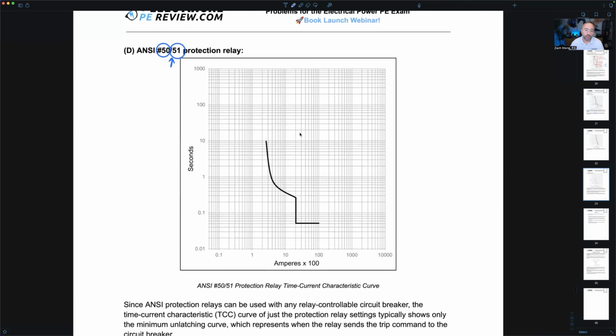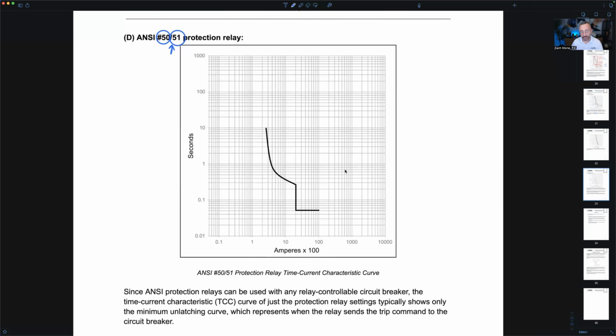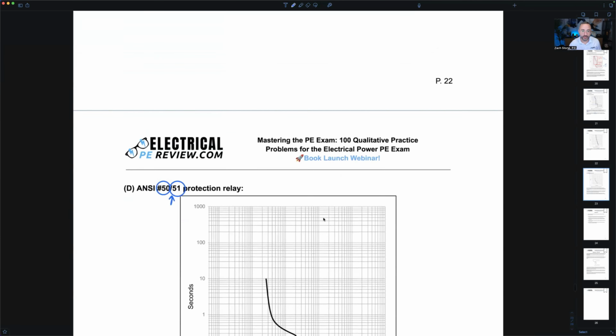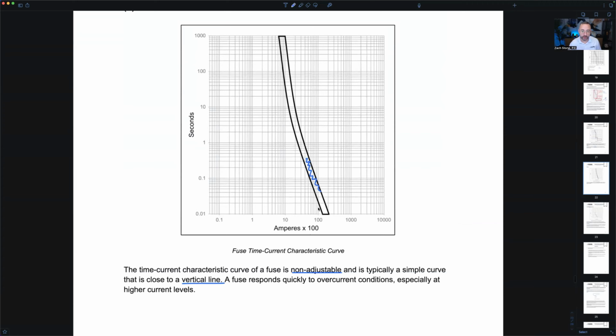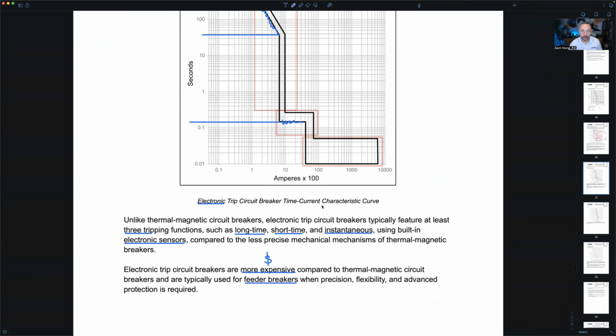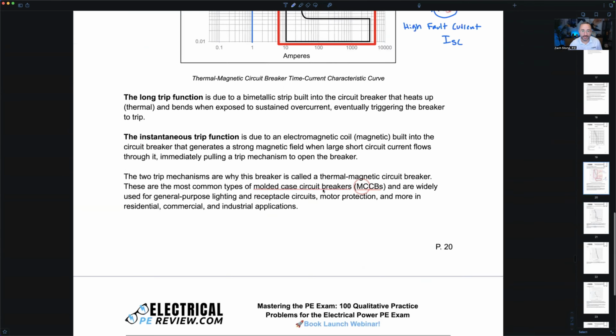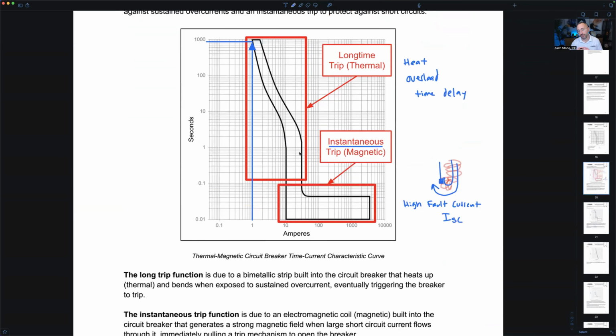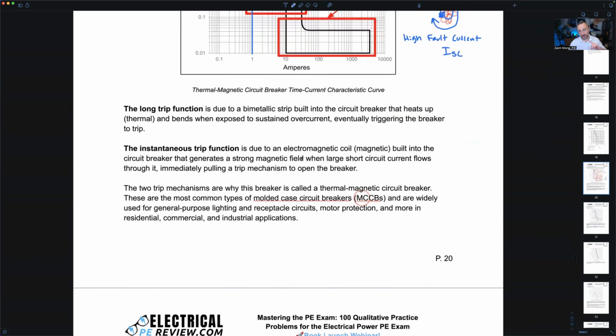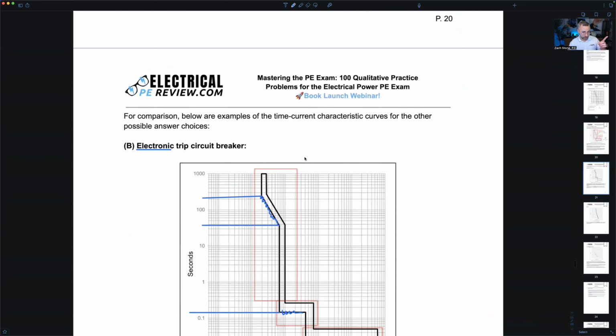But how do we know this is a relay? The dead giveaway is I only have one line. I don't have a region. So a relay by itself sends a trip signal, but it's the breaker that opens. So when I've got a region, like a trip region, either in a fuse here, or my electronic trip breaker, or my thermal mag breaker, that's the average time that it takes that device to physically open and clear the fault and disconnect it. Well, all the relay does, the relay just tells the breaker when to trip.